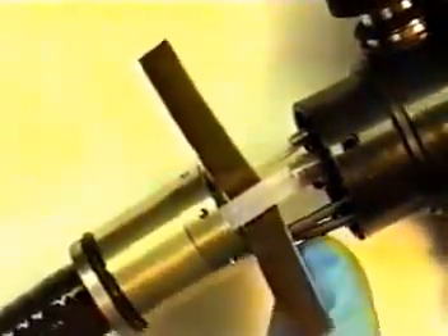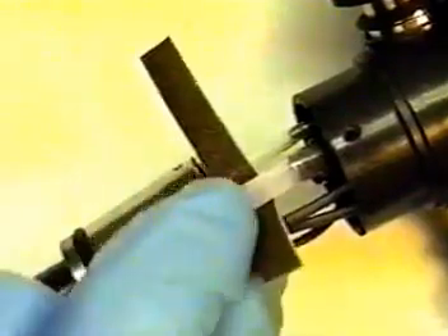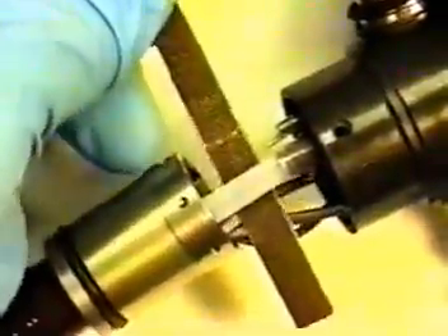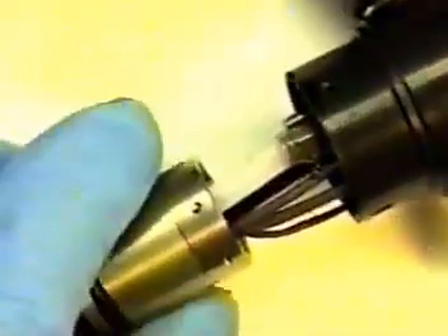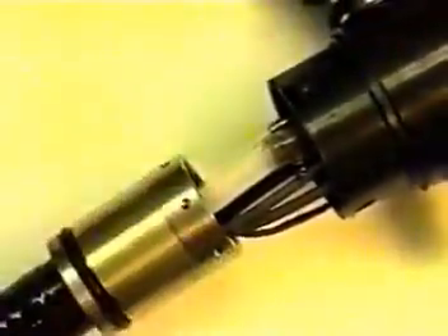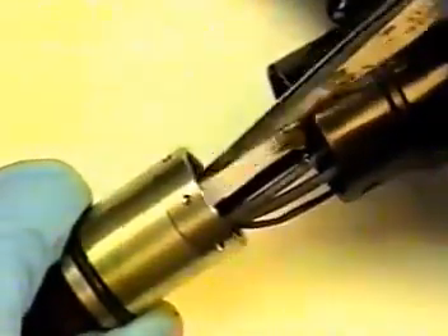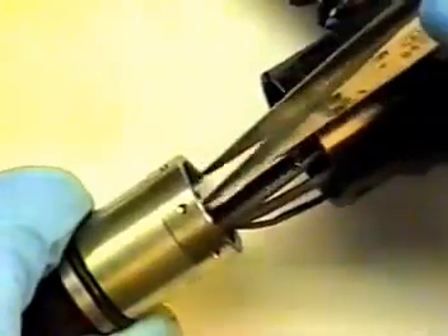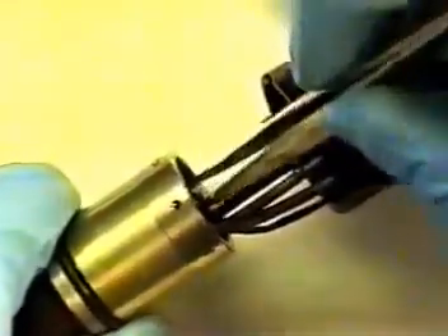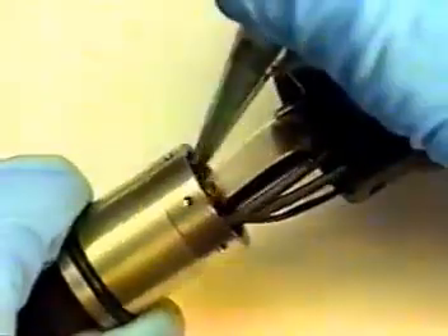Slide suction channel up and over suction port, pushing down and allowing suction channel to push completely over suction port. Be careful not to kink or touch any other tubing or your light guide bundles. Pull out your emery cloth. Retrieve the suction tubing clamp, which was previously slid down suction tubing.